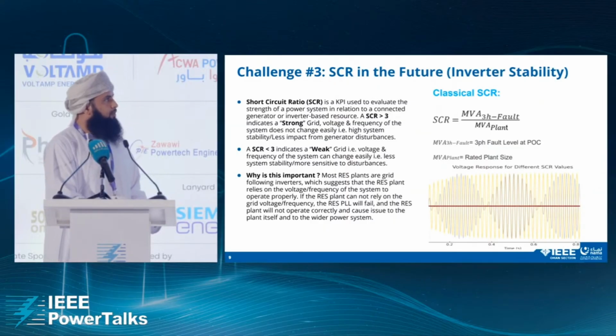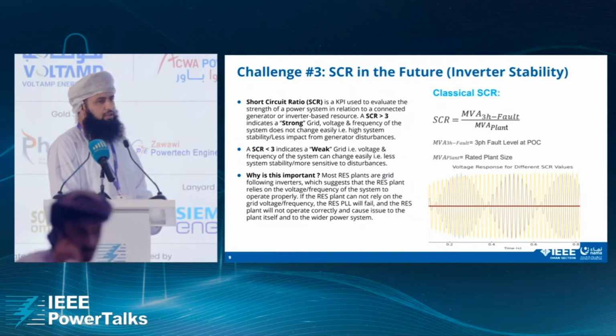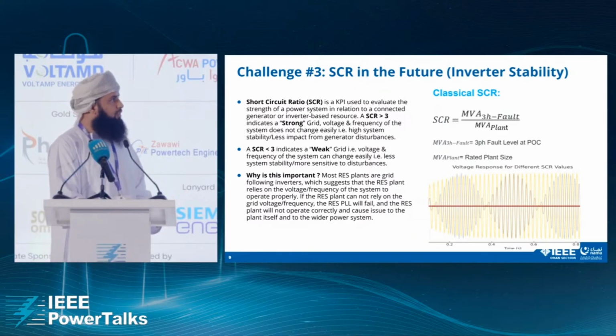One main element to measure the system strength is the short circuit ratio. If the short circuit ratio at the connection point of renewable energy is more than 3, it means that the voltage and frequency do not change easily. So that will give you an indication that we can integrate renewable energy into that connection point. However, having a short circuit ratio of less than 3 means that the grid is weak and cannot integrate a lot of renewable energy at that connection point. So we need to strengthen the system, for example with conventional generation to increase the short circuit.